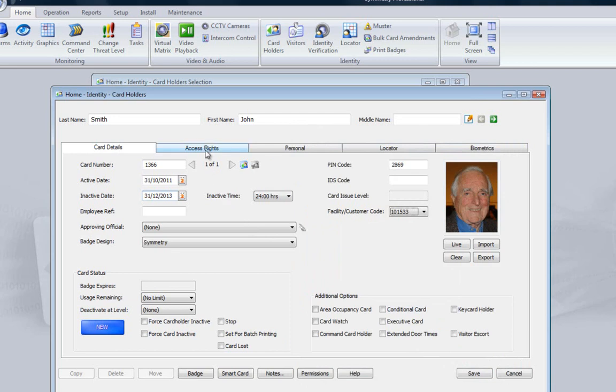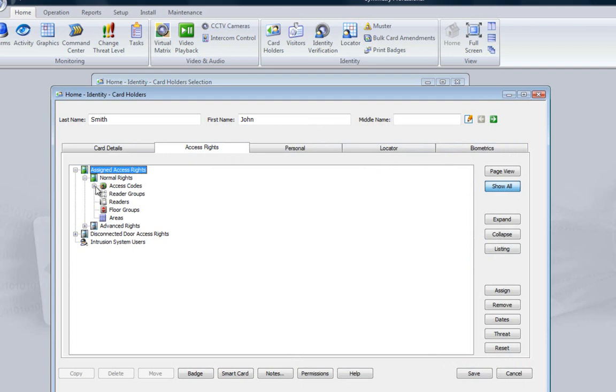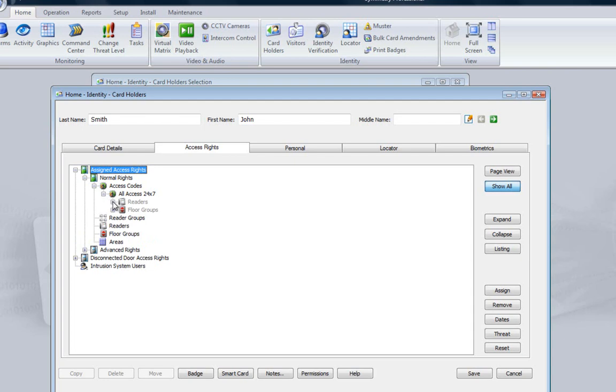The Access Rights tab defines which card readers this cardholder has access to. To simplify setup, combinations of card readers can be allocated to a particular badge design. So as soon as we allocated this cardholder to the Symmetry badge, it automatically had access to the following card readers.